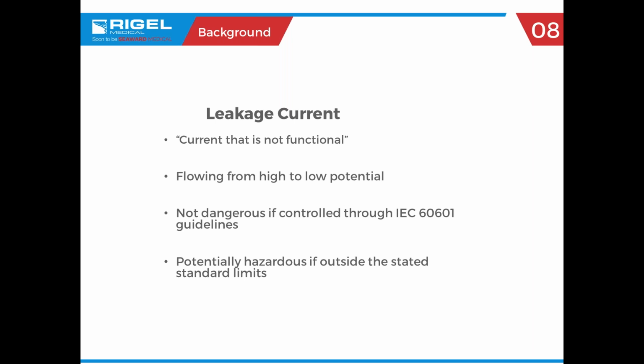As long as the leakage current stays within the range of the guidelines, it's considered completely safe. However, once that reading falls even just a little bit outside that range, it becomes a danger for both the patient and any of the staff.